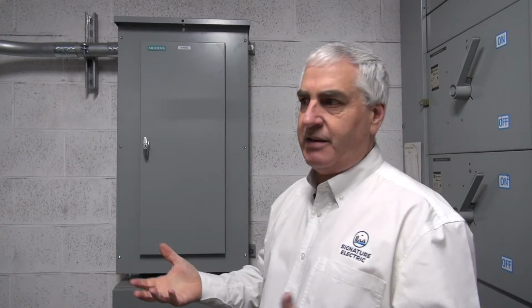Well, that's probably not a reality. People come home at different times. They're away. And it doesn't take all night to charge a car. So how can we incorporate that? That's what we've done in terms of the control. We've incorporated the idea that let's monitor the feed. As we reach a certain level, let's turn them on or off as is needed in order to try to have everybody have a full overnight charge, which we can continue to monitor because we have this live information.